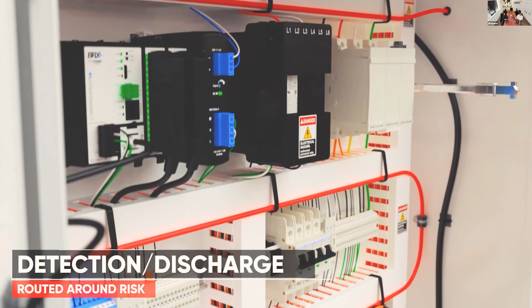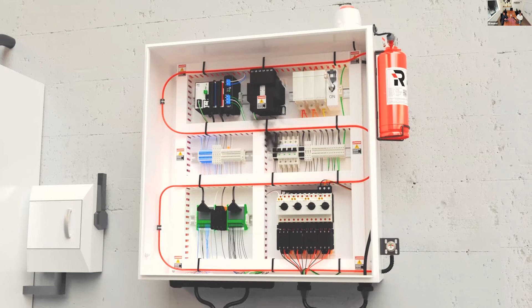The key to minimal fire damage is early detection and suppression. The Clean Agent Fire Suppression System from REACTON is installed directly at the point of fire risk, providing rapid detection and suppression. Typical fire hazards within electrical equipment include faulty wiring, poor maintenance, overloaded circuits, or outdated equipment. Systems can be configured to provide notification through onboard pressure switches and a battery-operated beacon sounder. The pressurized tubing is installed in and around the fire risks, always in communication with the system contents. When a fire occurs, the tubing bursts at the point of highest heat, and immediate discharge of the extinguishing agent starts at the point of detection, providing fully automatic fire suppression 24/7. Simple integration to your building alarm or management system is also very easy.